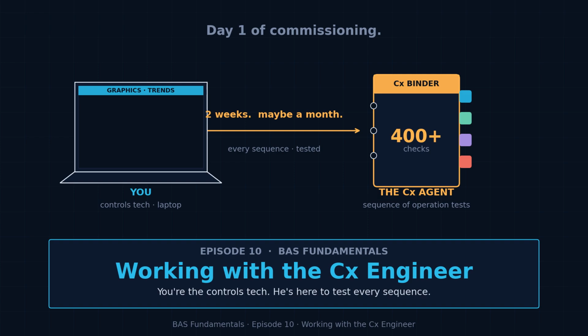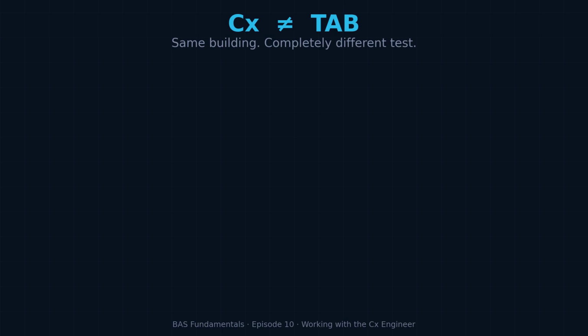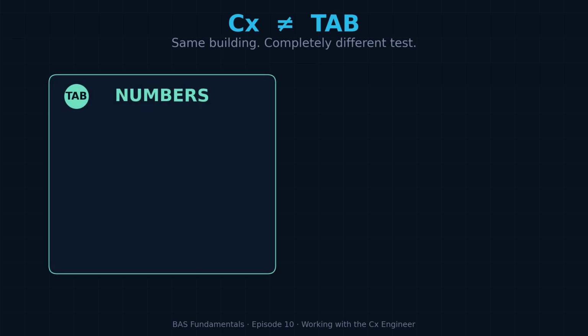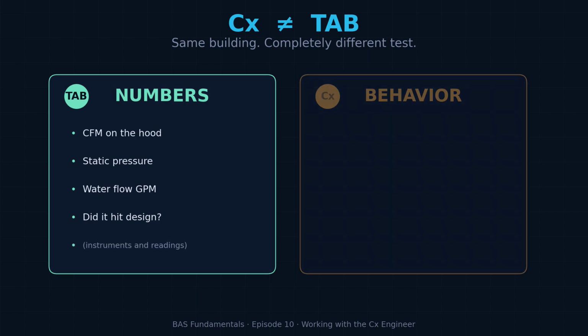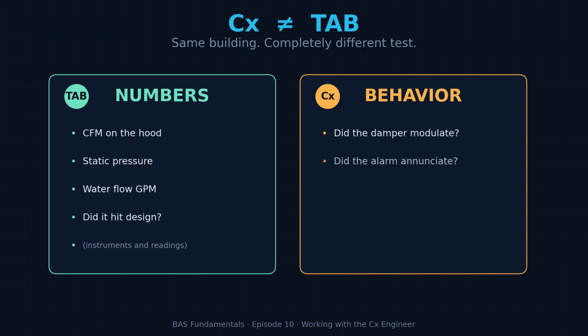For the next 2 weeks, maybe a month, he is going to test every sequence of operation in this building, one at a time, against the design. And you are going to sit next to him while he does it. Let's be clear about what this is. TAB was about numbers. CFM, static pressure, water flow. The CX agent doesn't care about numbers the way TAB does.